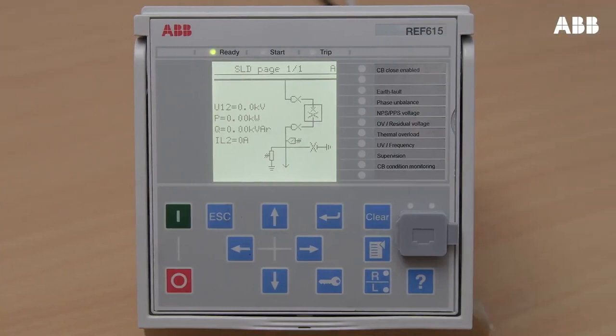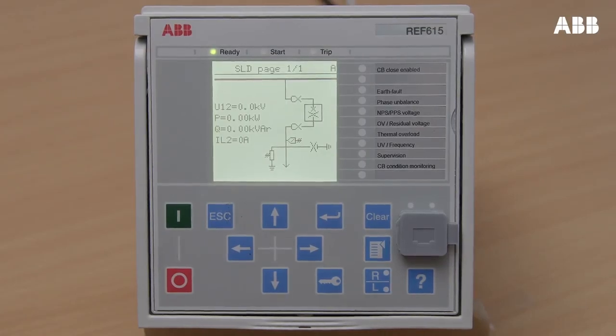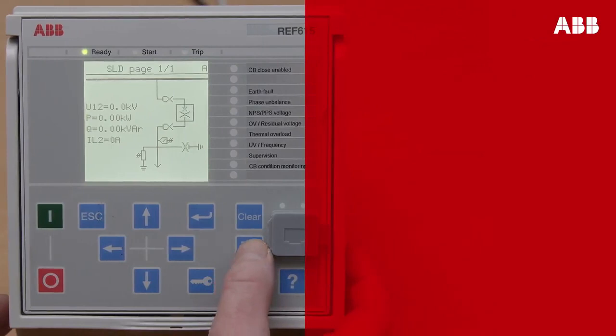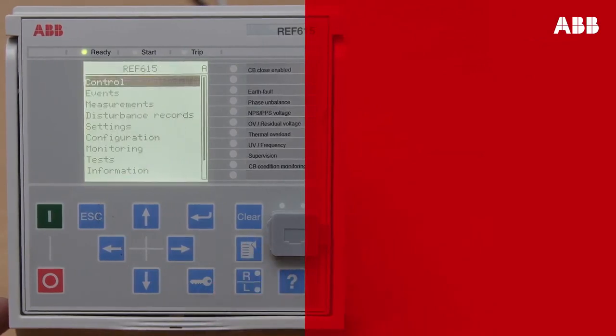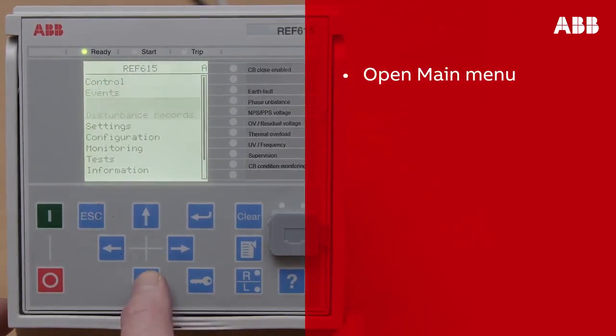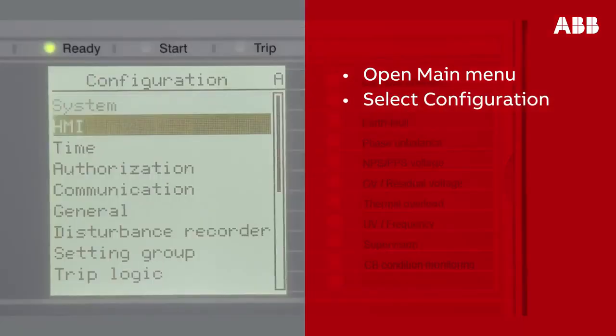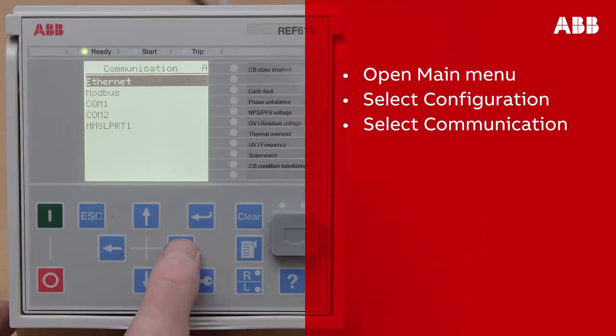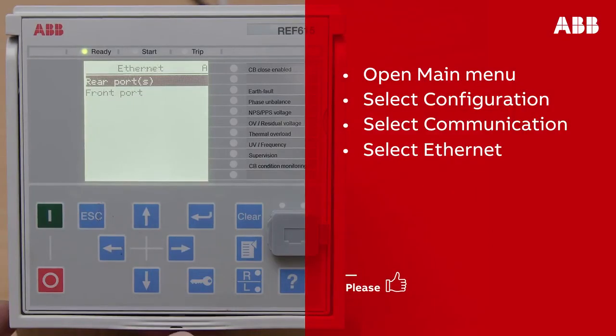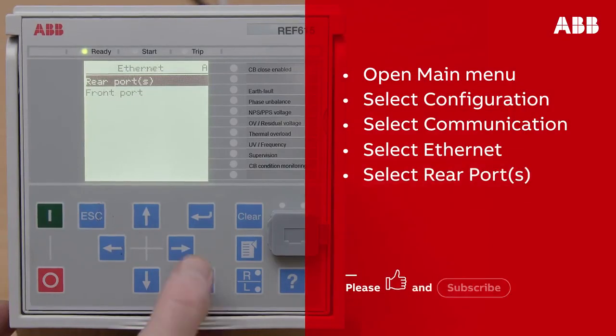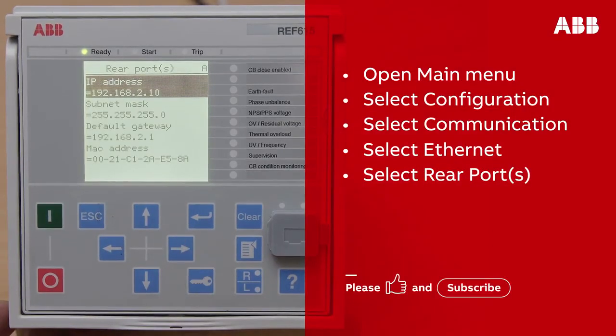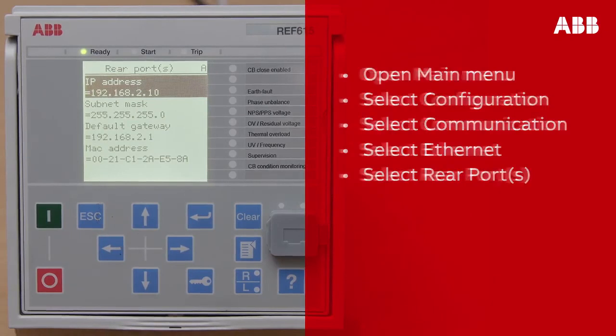If you are using the rear port, you will need to manually change the laptop's IP address to one that is on the same sub-network as the relay's IP address in order to connect to the relay. To get the relay's IP address, browse through the menu on the relay LHMI to select Configuration, then select Communication, select Ethernet, and then select Rear Ports. Here you can see the IP address for the relay.